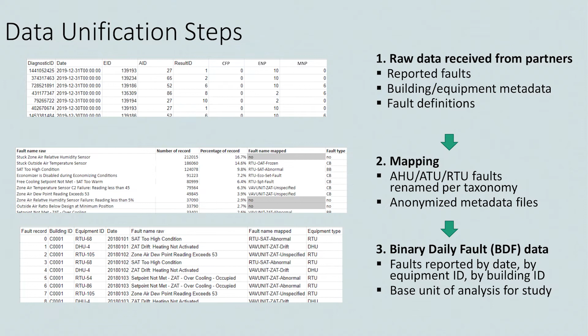Now, even though FDD tools can report things that happen for 30 minutes or an hour, maybe there's a trigger threshold to say something's off or something's cycling, we had to find a way to unify that to a higher level, which was daily for us. So daily means a fault happened for some portion of that day, could have been 24 hours or just 1 hour, but we had to standardize on something.